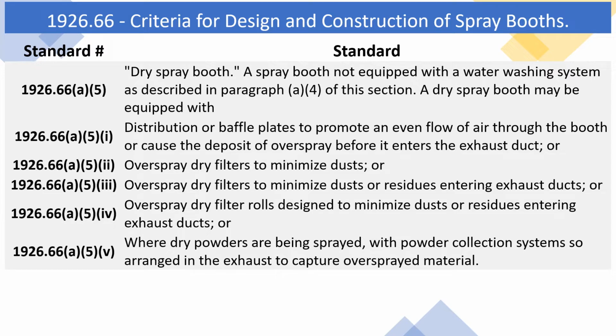1926.66 A.5. Dry spray booth. A spray booth not equipped with a water washing system as described in paragraph A.4 of this section. A dry spray booth may be equipped with 1926.66 A.5.i. Distribution or baffle plates to promote an even flow of air through the booth or cause the deposit of overspray before it enters the exhaust duct, or A.5.ii. Overspray dry filters to minimize dusts, or A.5.iii. Overspray dry filters to minimize dusts or residues entering exhaust ducts, or A.5.iv. Overspray dry filter rolls designed to minimize dusts or residues entering exhaust ducts, or A.5.v. Where dry powders are being sprayed, with powder collection systems so arranged in the exhaust to capture oversprayed material.